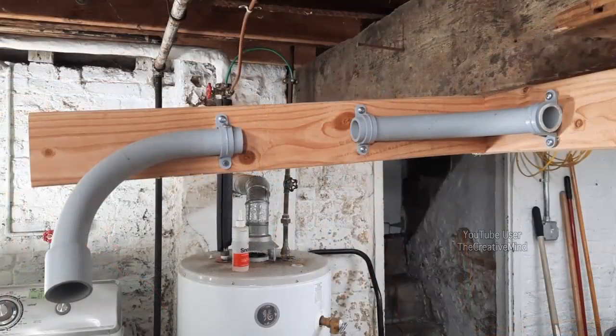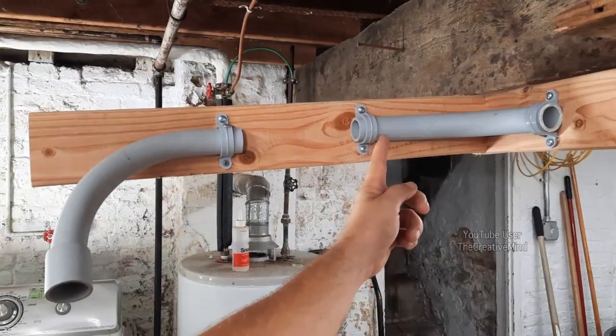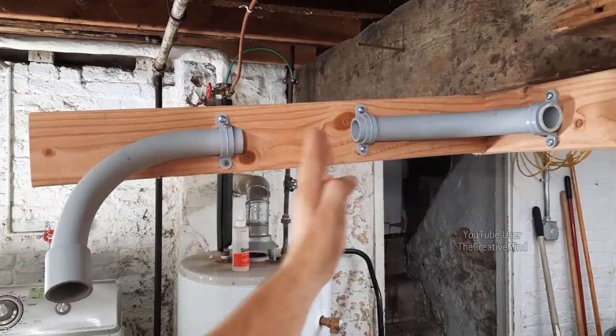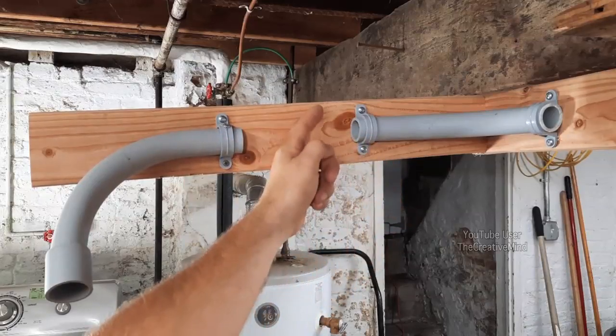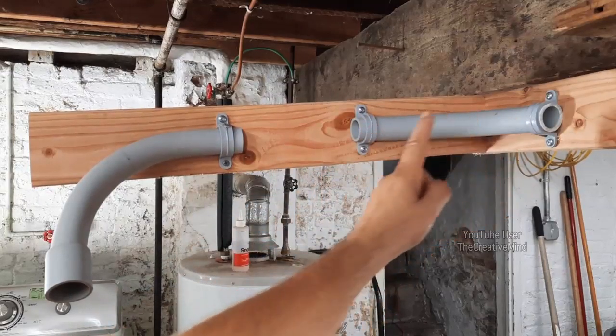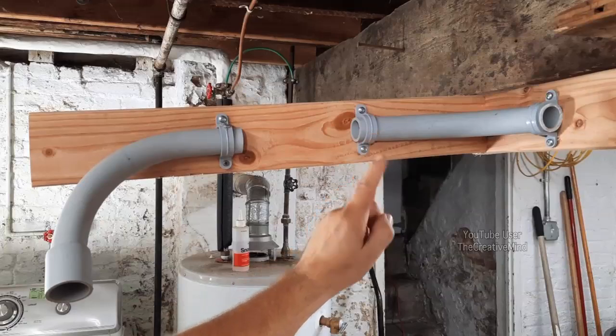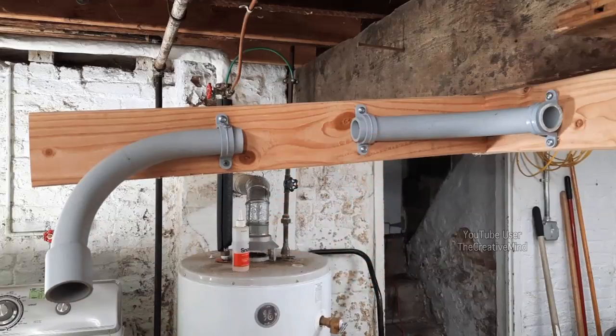We're going to install these electrical 1-inch 90-degree PVC elbows on our train table frame, and we're going to secure them at each end with a 2-hole 1-inch PVC strap using number 10 by 1/2 inch long screws.